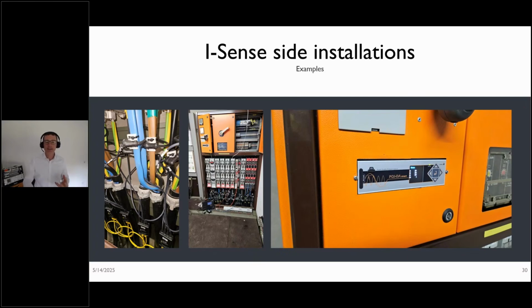As you can see, it's really easy in the case of a daisy chain. The iSense is installed directly at the cable, with Rogowski coils on L1, L2, L3, or possibly neutral - though that's not a must in my opinion. With an RJ45 plug, you can daisy chain this technology through the whole substation, bring it into our device, and then the whole substation is digitalized. The main point is how easy it is to install.